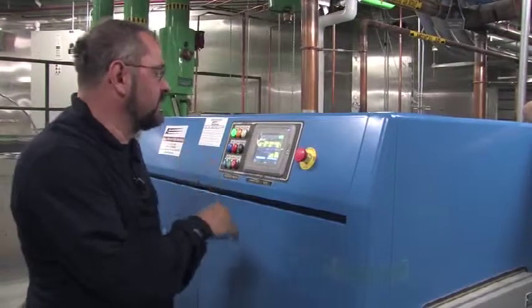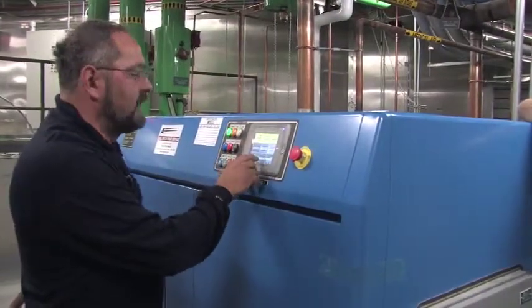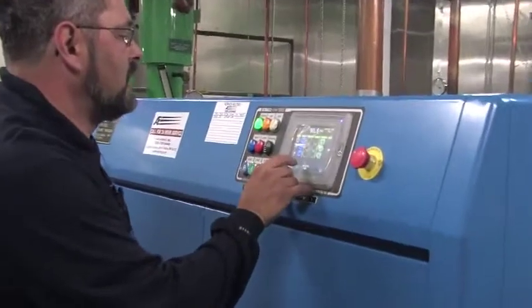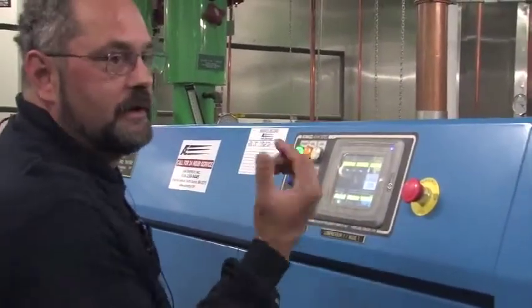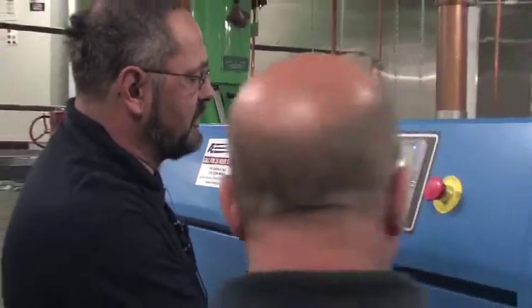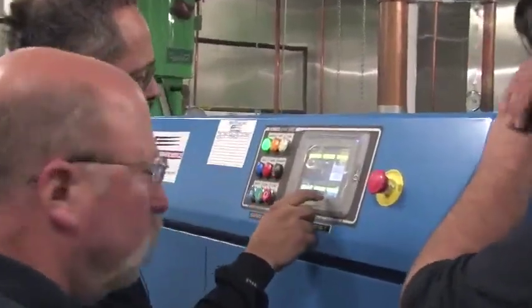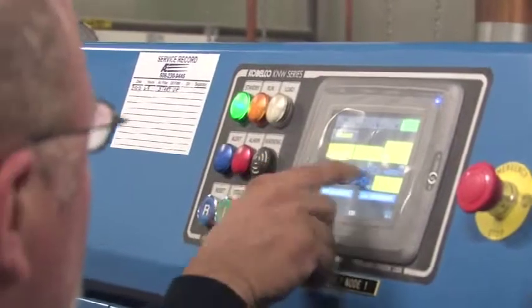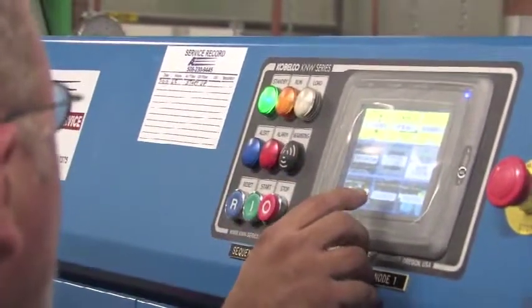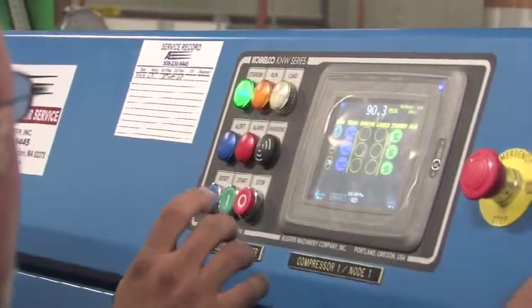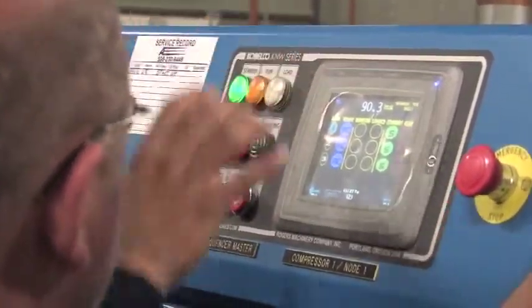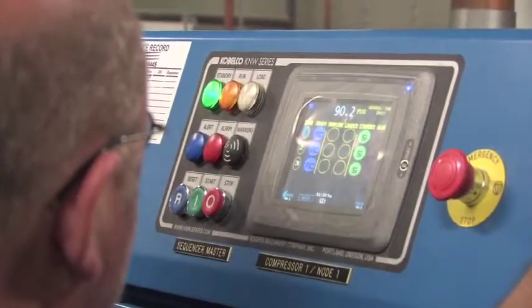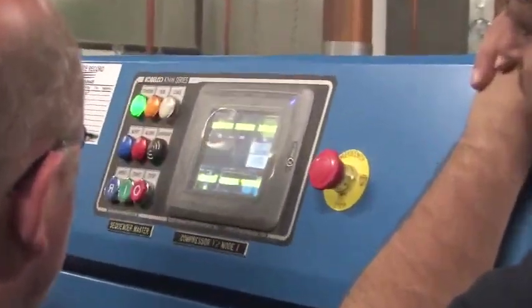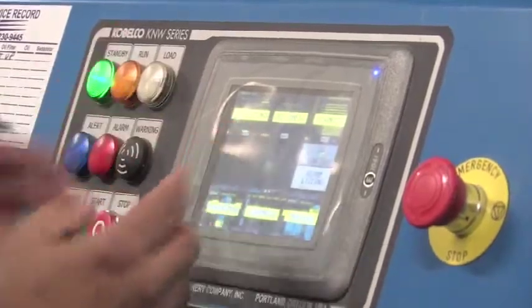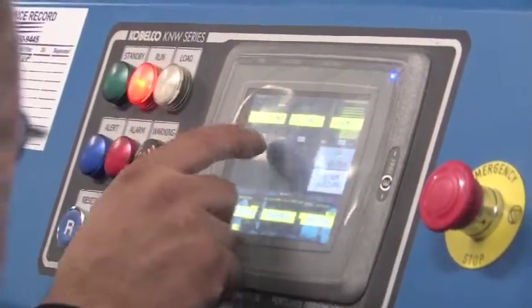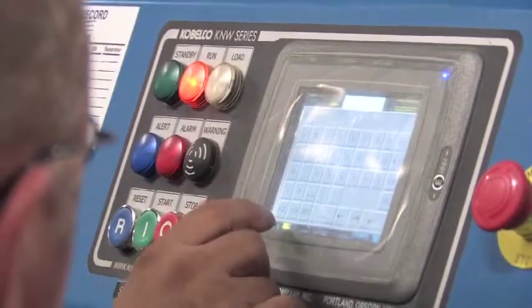Yeah, the sequencer. Now what we were talking about as far as the sequencer, the set points for that, just so you know the way to get into that in this machine: when you go to the main panels, you get the sequencer button, you touch that, and this comes up. Now to get into the sequencer menu, think of it as a whole separate program, a separate device. I have to hit the center of the screen again, just like we do on the main one. And now I get the sequencer configuration stuff and diagnostics.